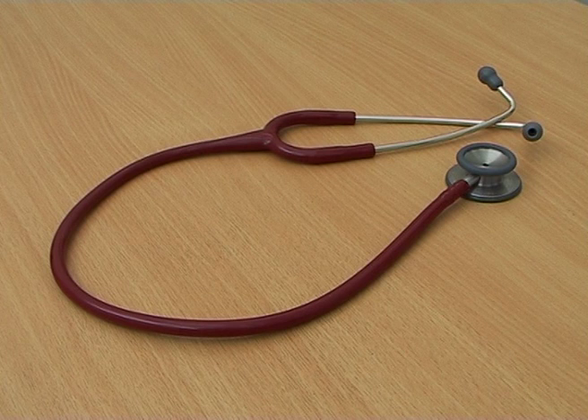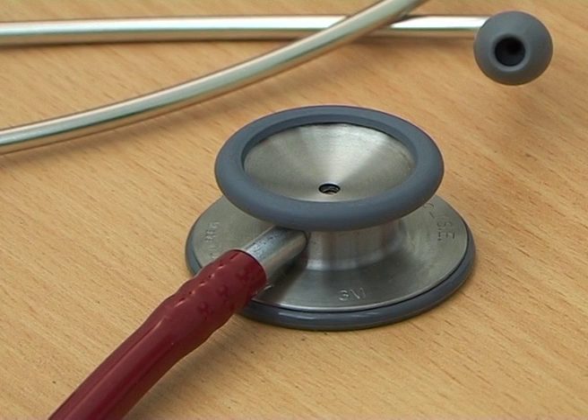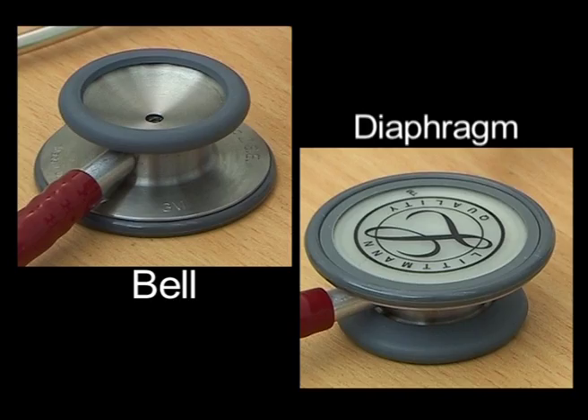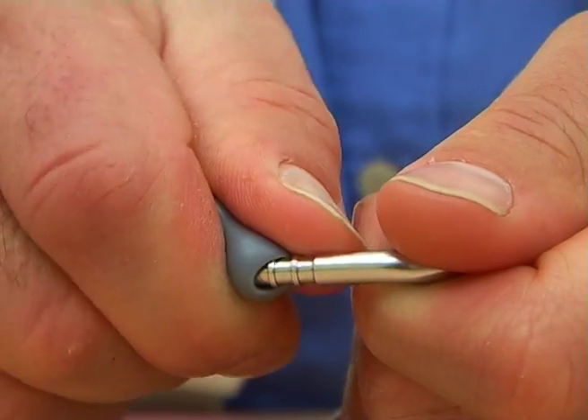Let us now look at the stethoscope. This is a simple device made up of a chest piece, a hollow plastic tube, and two earpieces. The chest piece is what you use to pick up the sounds, and it is usually double-sided, made up of a diaphragm and a bell. The sounds from the chest piece are transmitted via the hollow tubing to the earpieces, whose ends are connected to two soft ear tips which can be removed for cleaning or replacing.